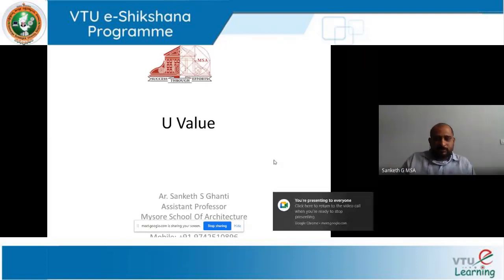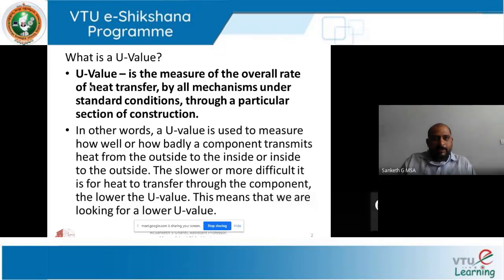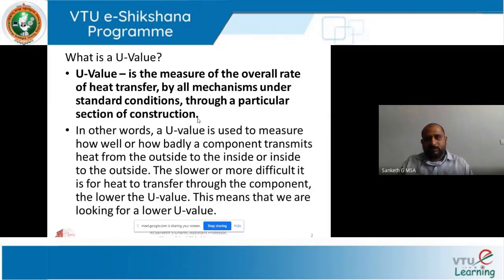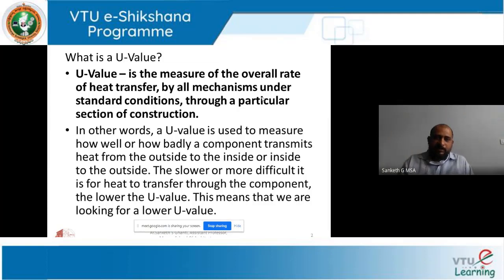U-value — please pay attention, this is a very important topic because you can do exercises based on this. I will just read out the definition: U-value is the measure of overall heat transfer by the mechanism under standard conditions through a particular section of construction. It can be a wall, it can be a roof — a particular section of construction. It is a measure of overall heat transfer, or it is a conductance value. The heat flowing from outside to inside or inside to outside through a material can be expressed by U-value.